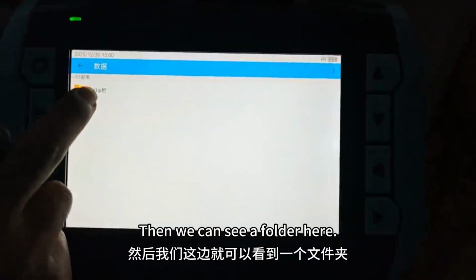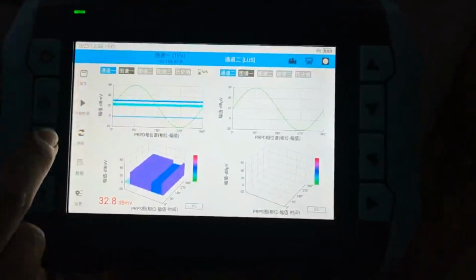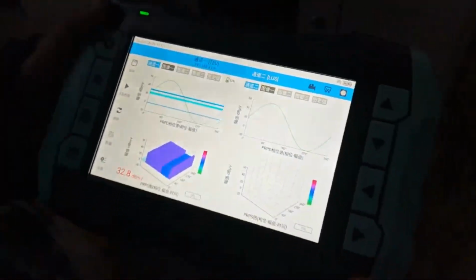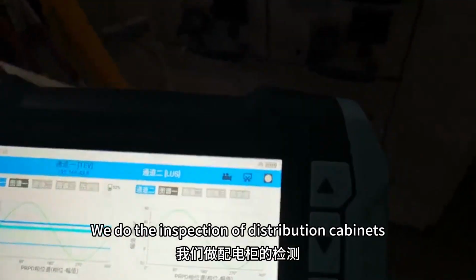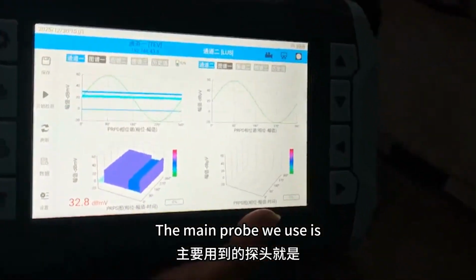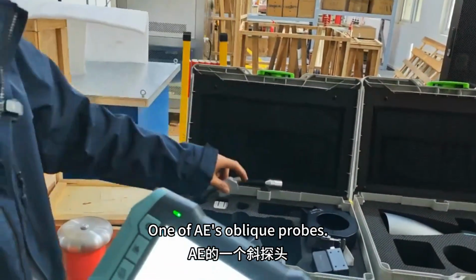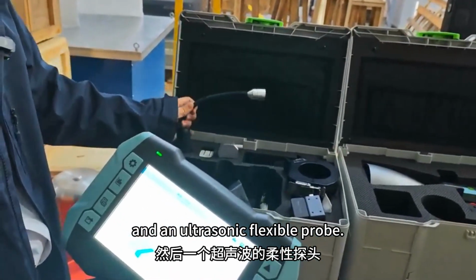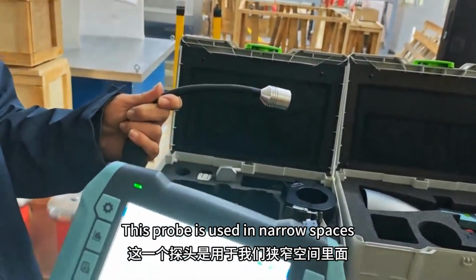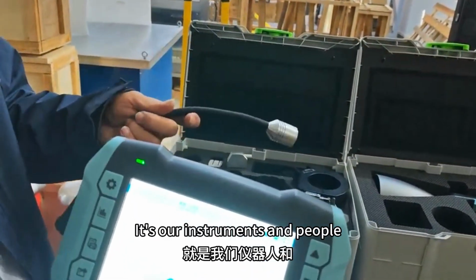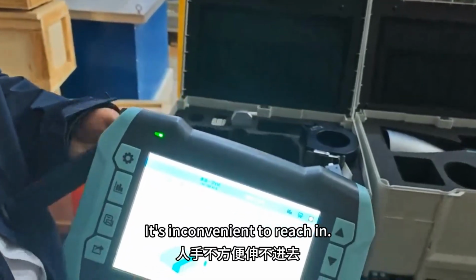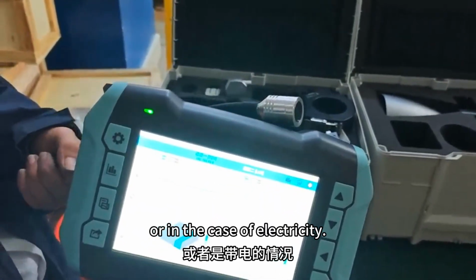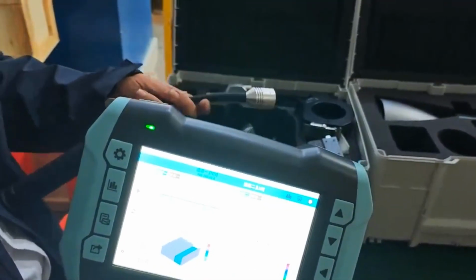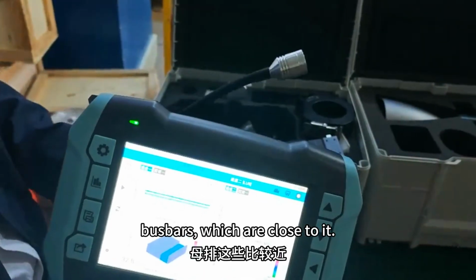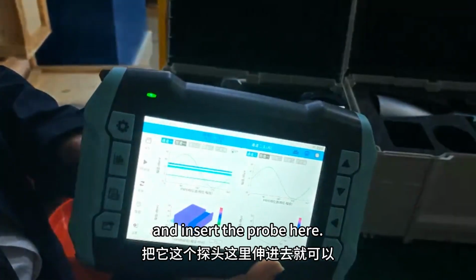Then we can see a folder here. Now we can start the inspection. We do the inspection of distribution cabinets. The main probes we use are the oblique probe and the ultrasonic flexible probe. This probe is used in narrow spaces, where it's inconvenient for our instruments and people to reach in, or where live bus bars are close by. And insert the probe here.